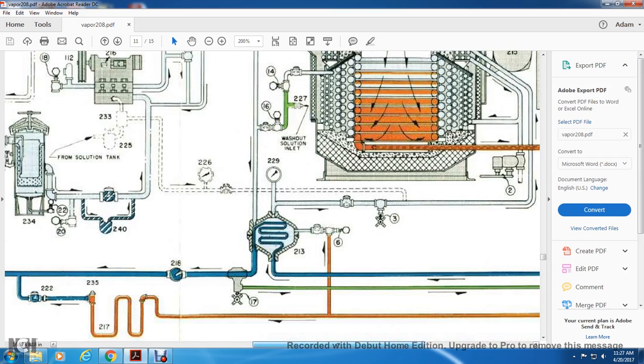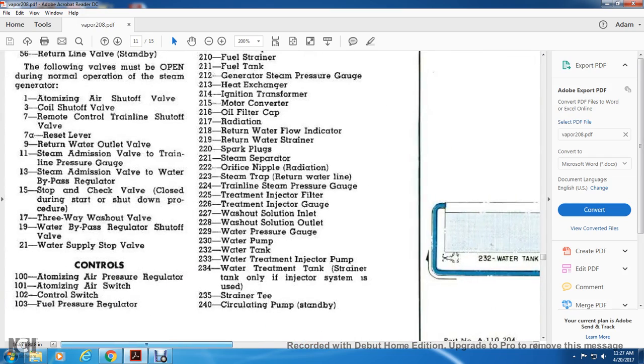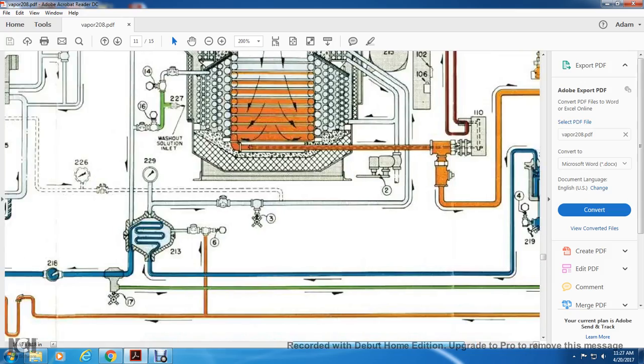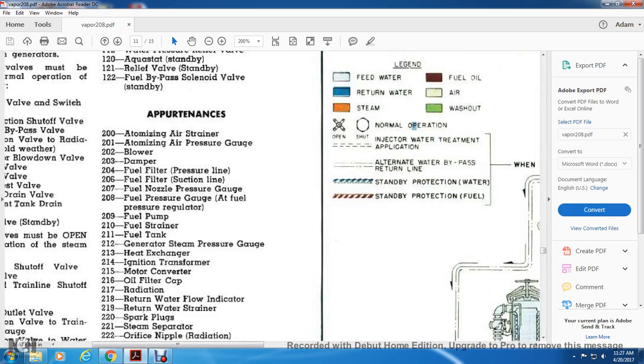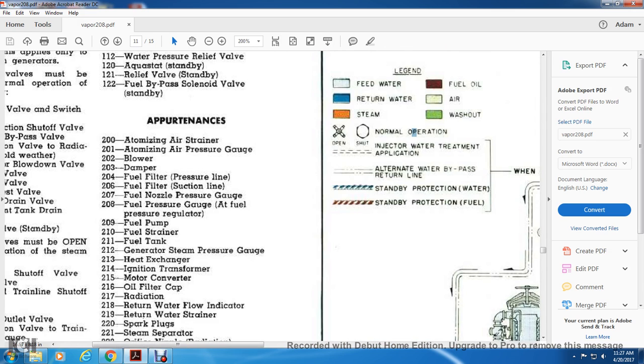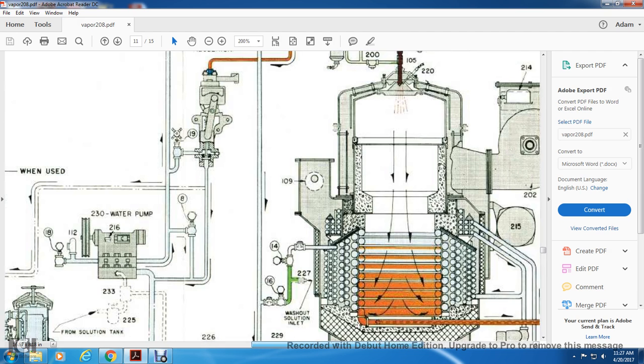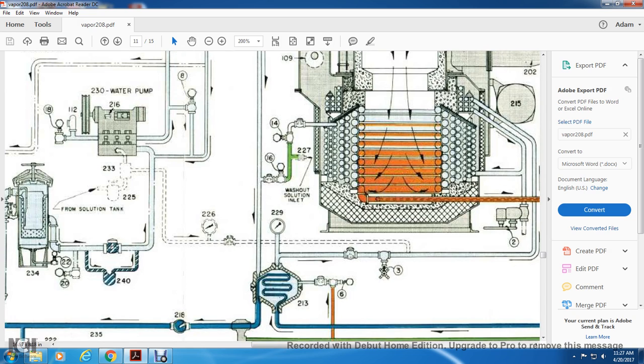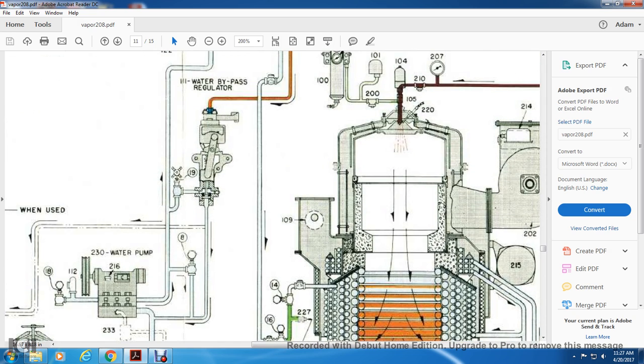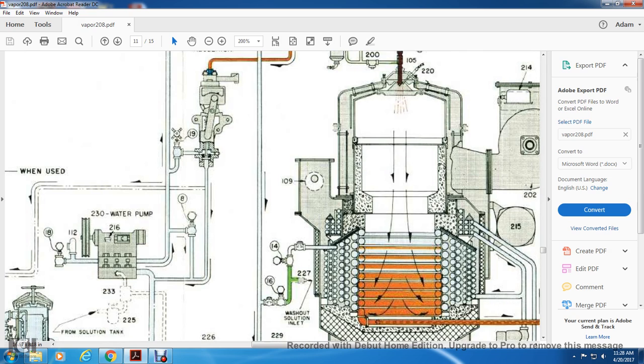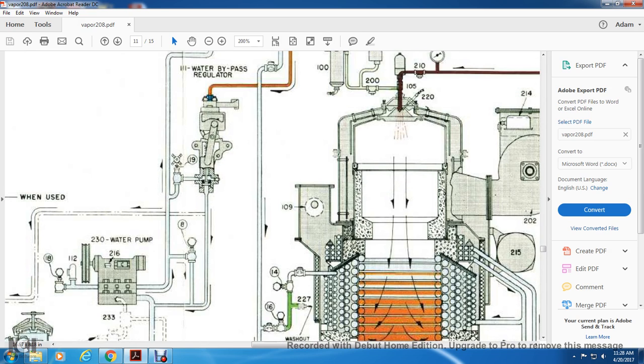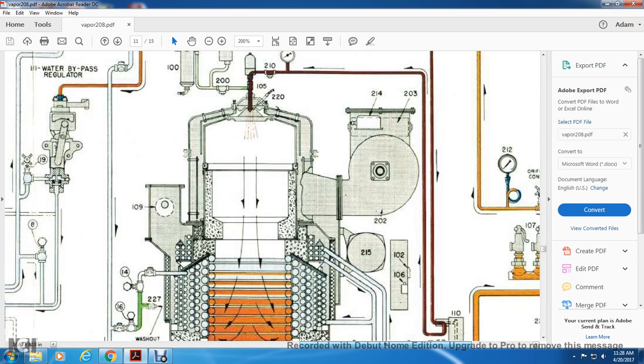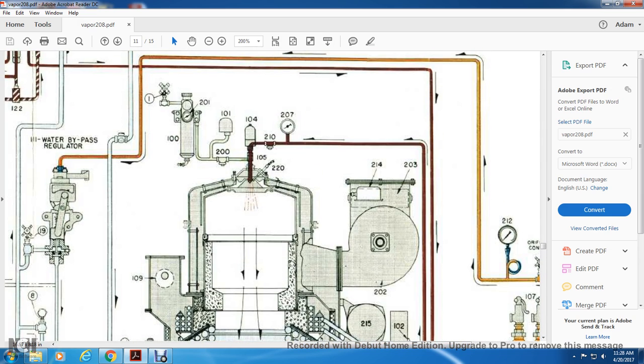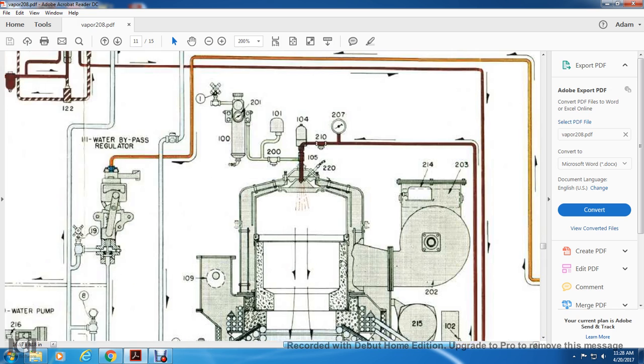And there's 17 through a wash valve, which has orange, green, and blue: steam, return water, and washout. The one from the servo control goes to the back side of the washout solution inlet, and then joins into the steam generator. At the top, there's a whole bunch of gauges.